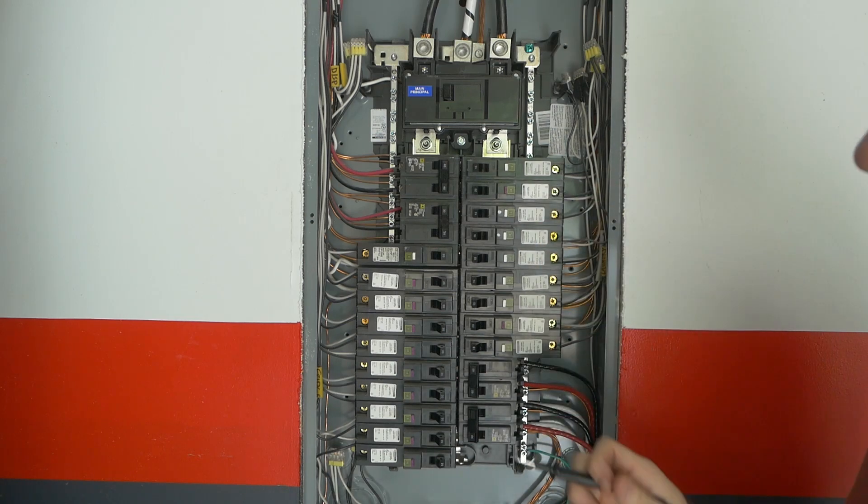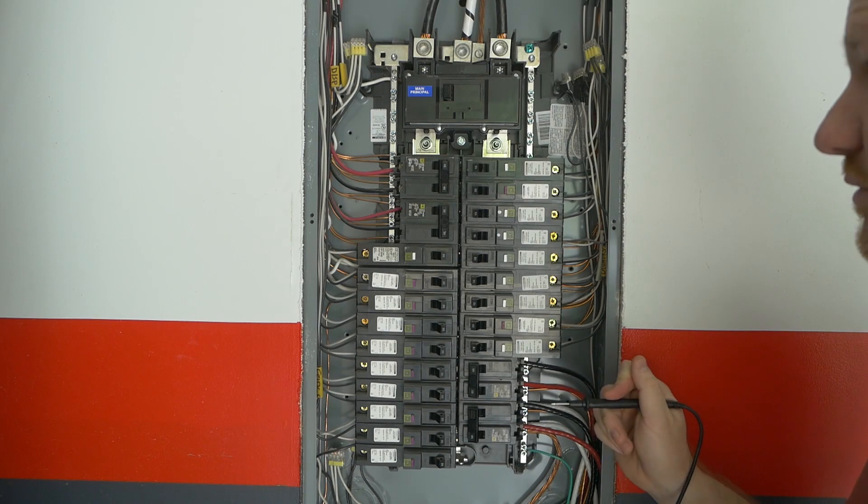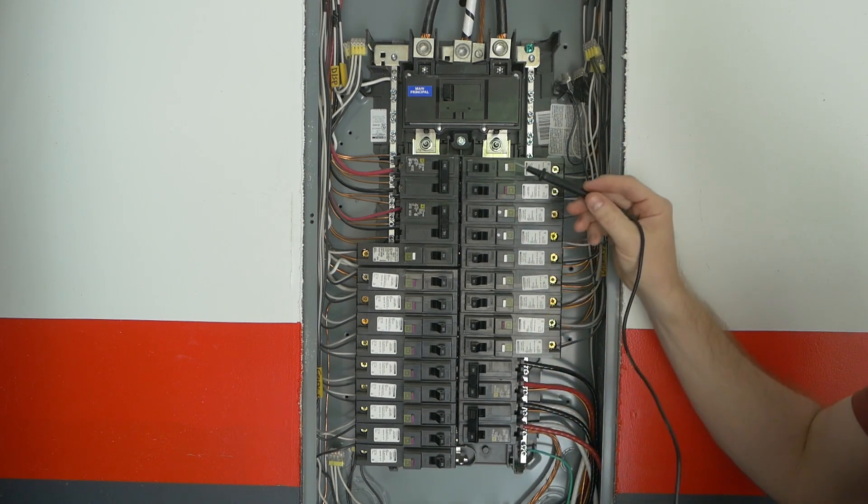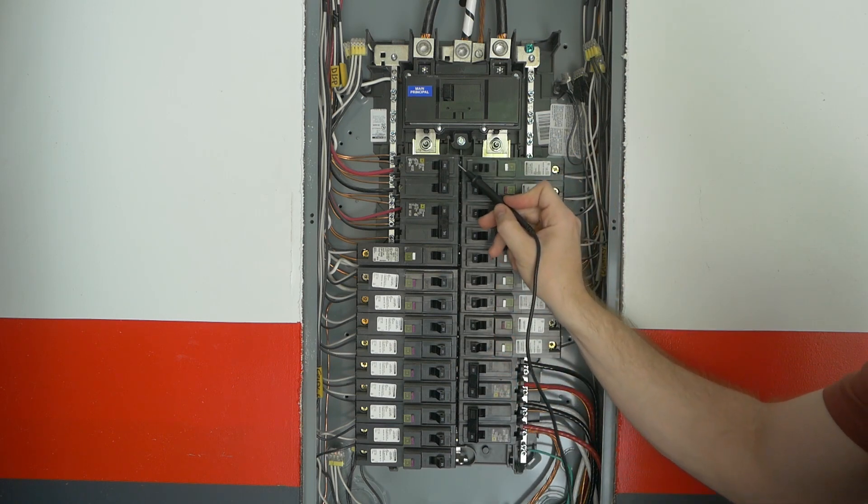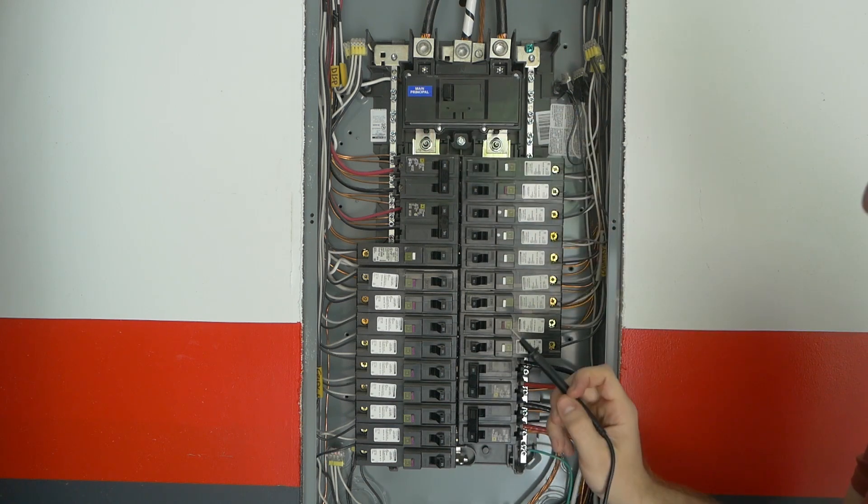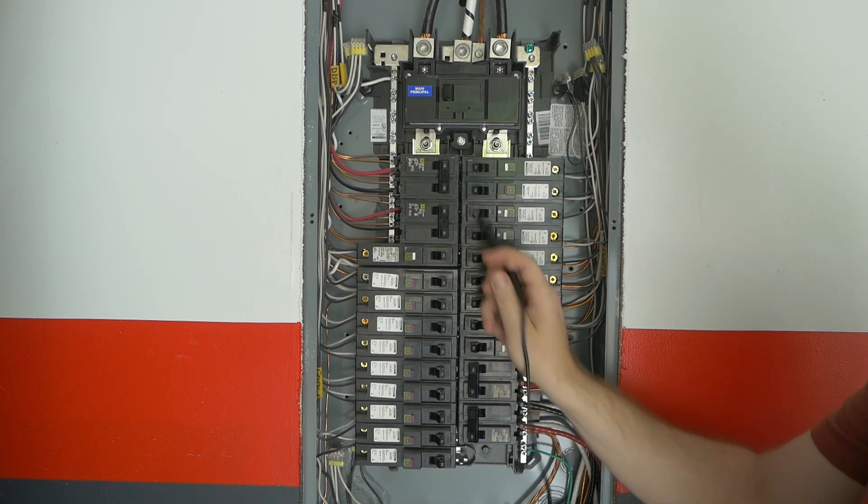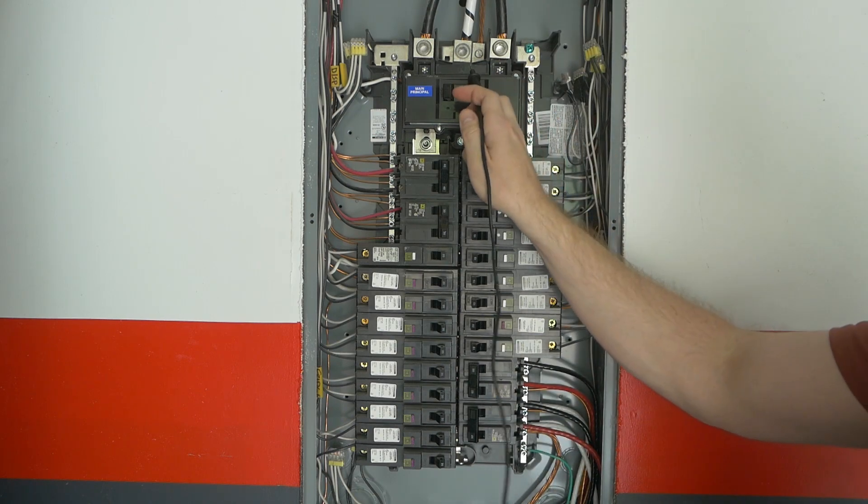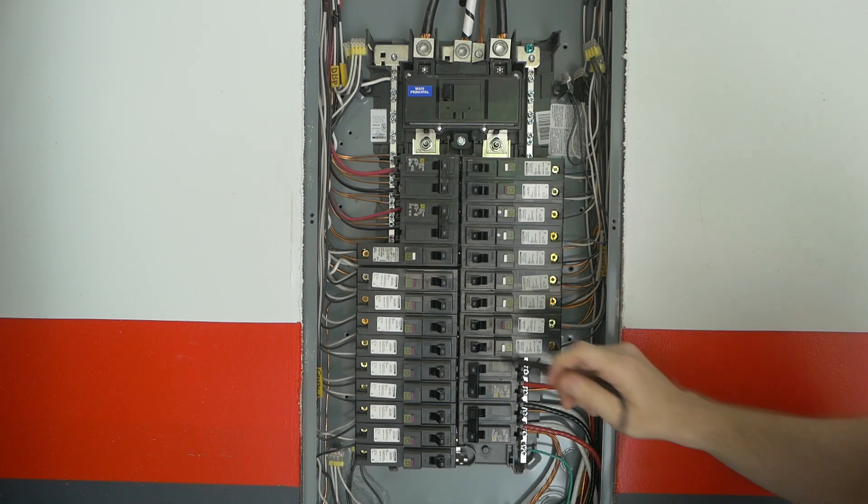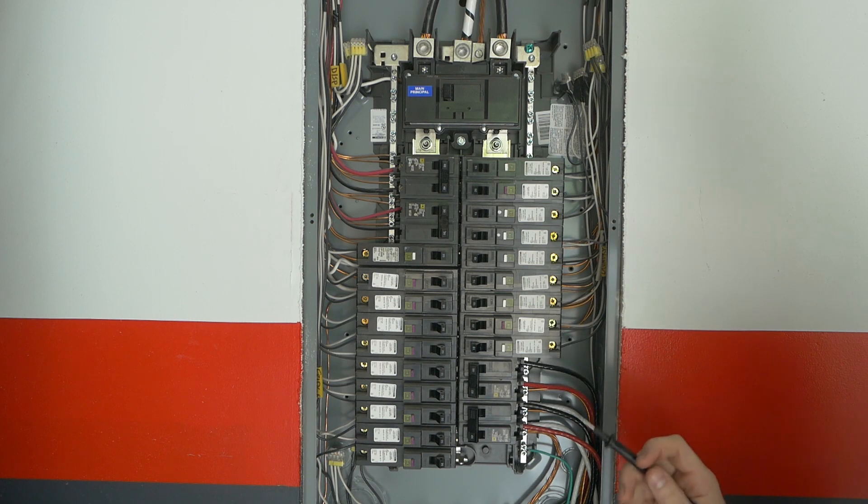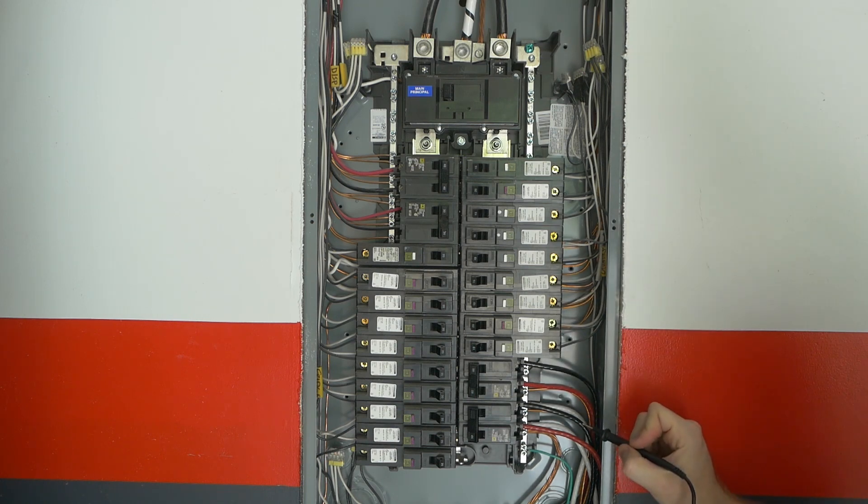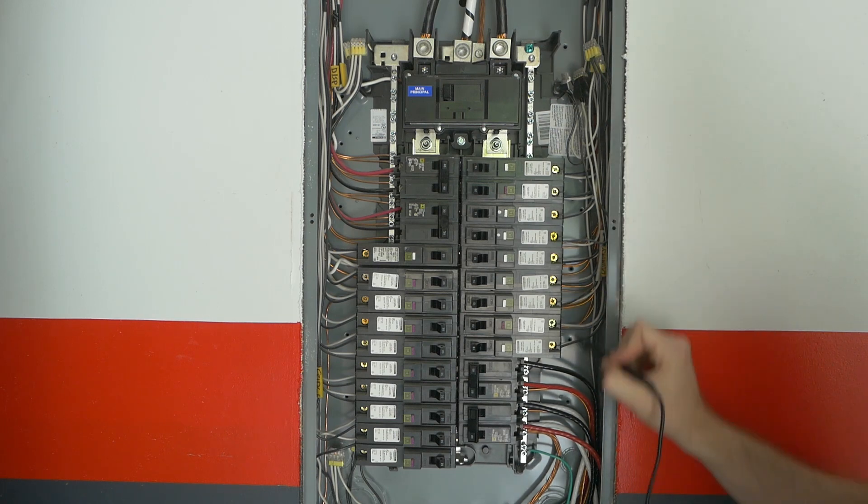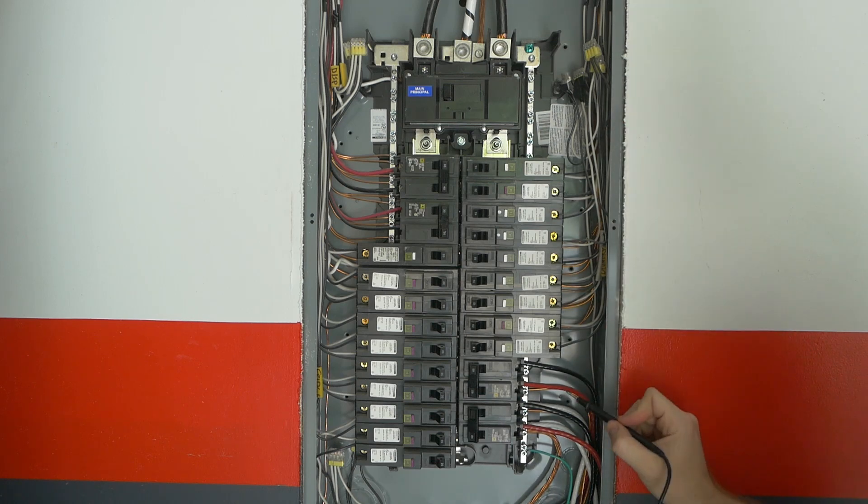Now we go down on these breakers and we see that some of them are these two pole breakers tapping both phases to get our 240, and then the individual breakers are just tapping one of these two at a time to get our 120. This neutral right here is actually distributed left and right to these two bars, so all these circuits are going to both tap some hots and some neutrals. Some of the pure 240 volt circuits, which I'm not actually sure even exist in this current panel, but if you had a pure 240 volt circuit it would actually not tap that neutral, although it would tie into it for the ground.